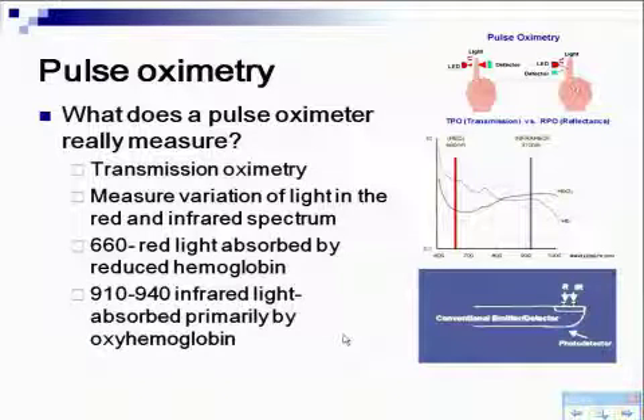Okay, so you put your clip on. The clip on has a certain amount of pressure, but the way the machine is actually measuring it is by looking at the thickness of your finger. When the pulse wave comes into it, your finger gets slightly thicker. Every time your arterial pulse hits you, your finger bounces.